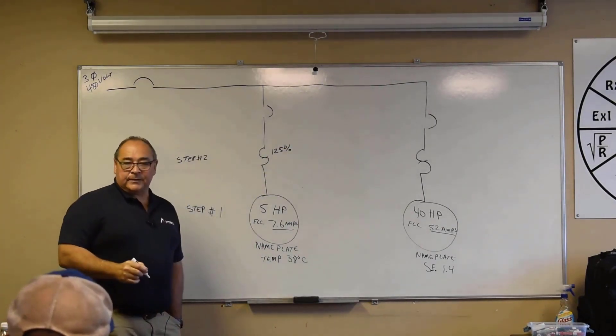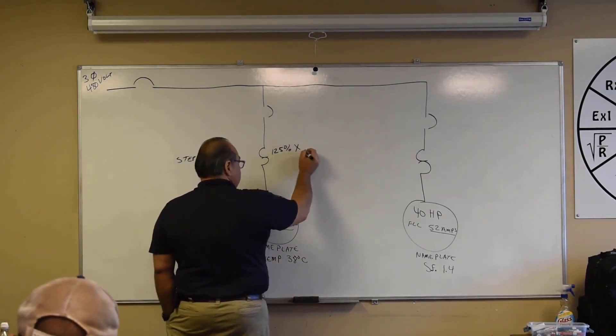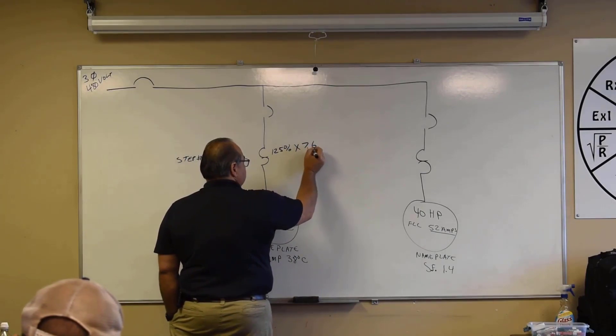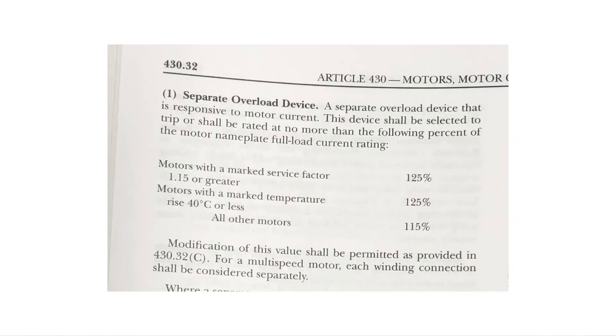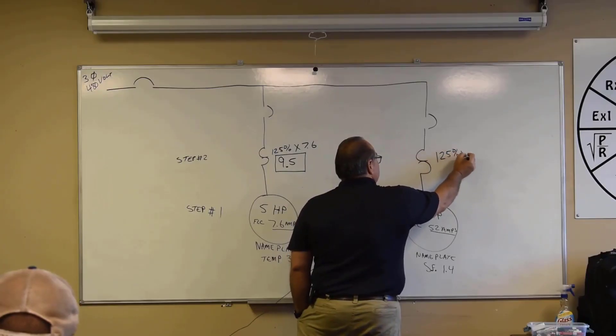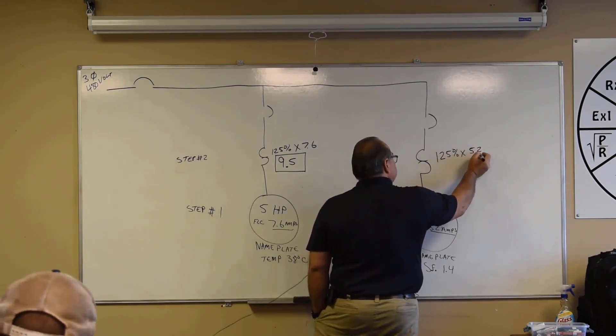Now over on the 40 horsepower motor, we got nameplate information, we got service factor 1.4. What's our percentage we're going to use over here? 1.15 or greater, and we're at 1.4. So 125 percent times what? Our full load current is 52 amps, right? What's that equal? 65 amps.